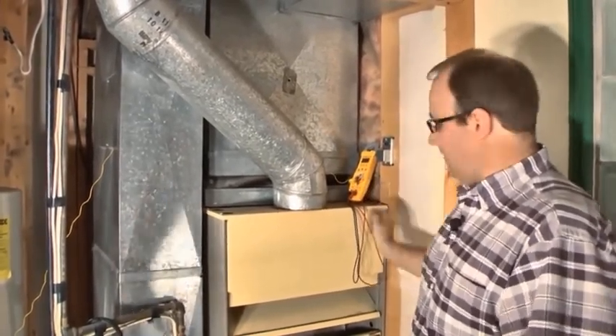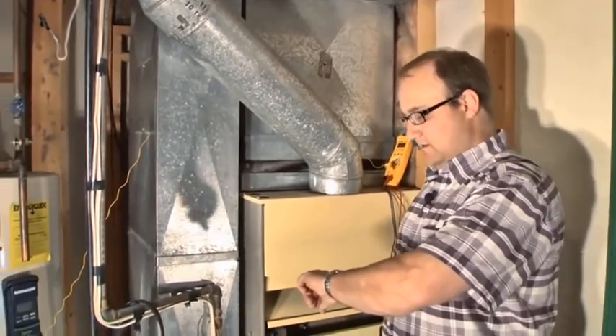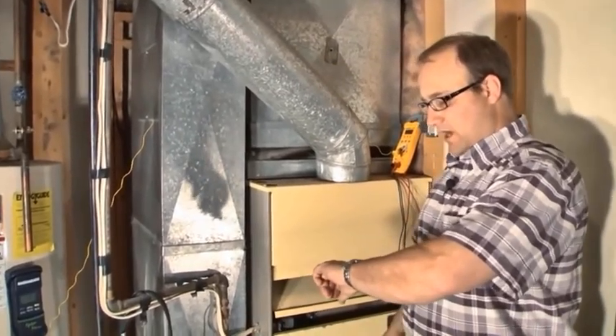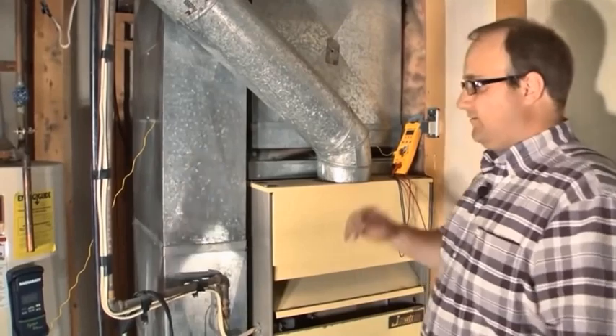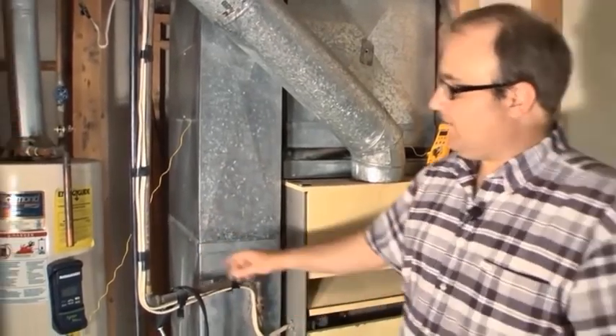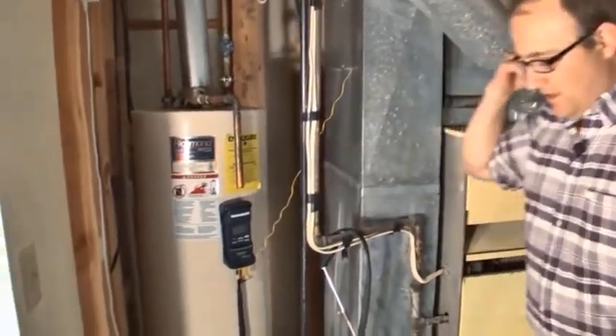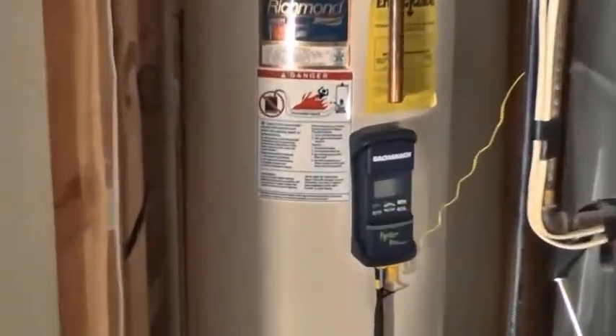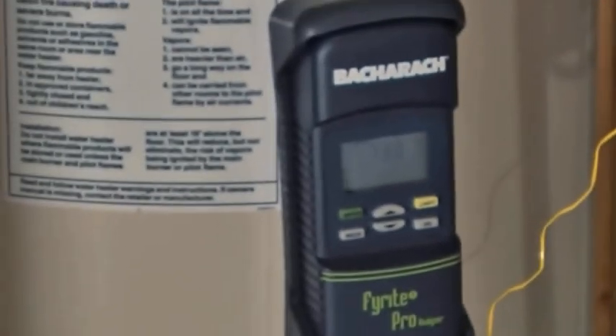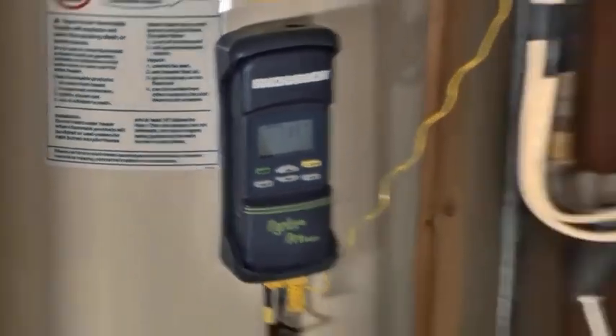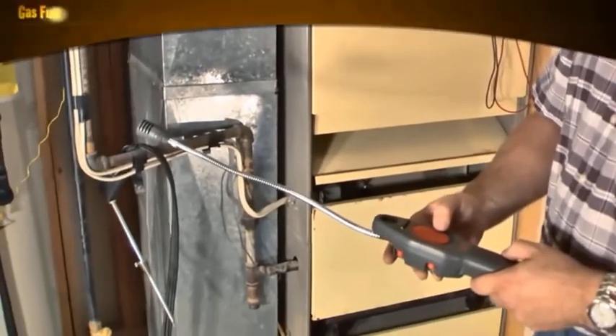This takes a little while. I usually time it with my watch. I've got a pretty good idea from there. I can see my return air temperature. While I'm waiting, a lot of times what I'll do is check for gas leaks on the piping around here, and I have a sniffer for combustible products.